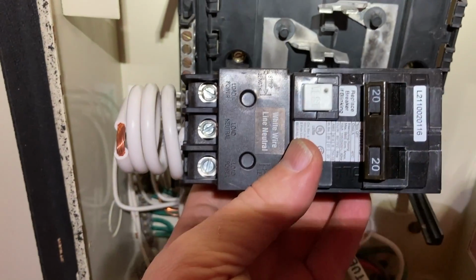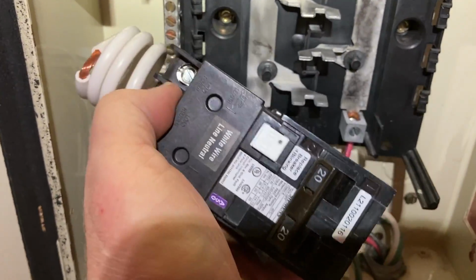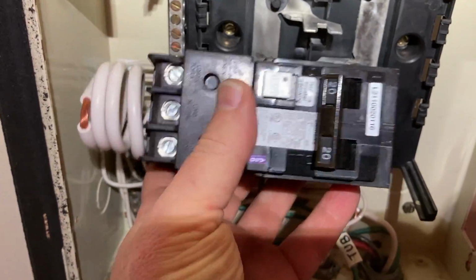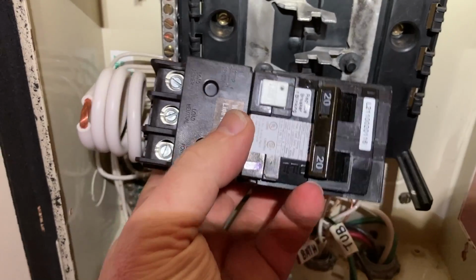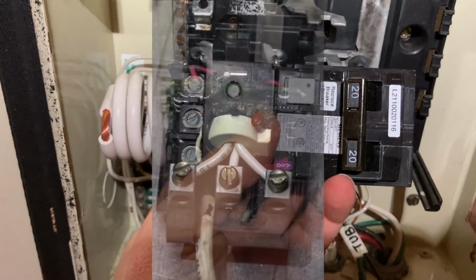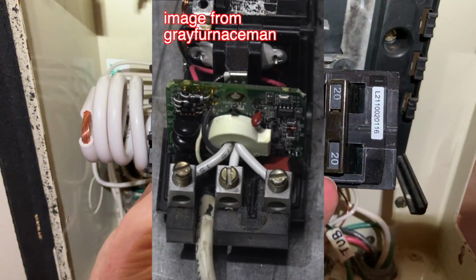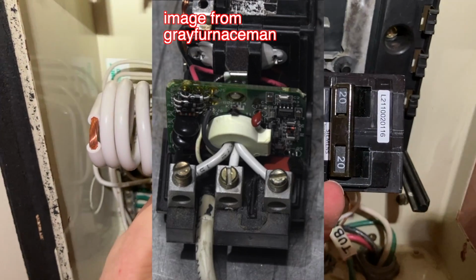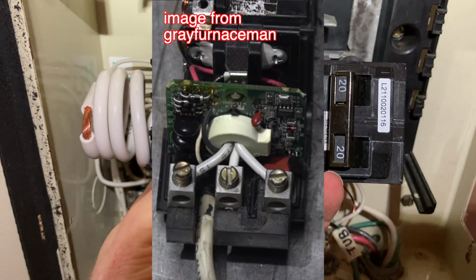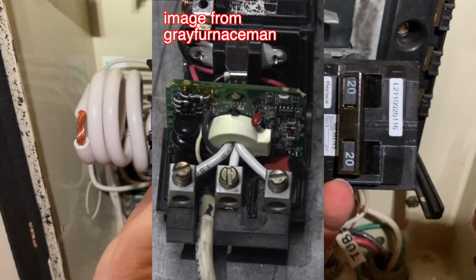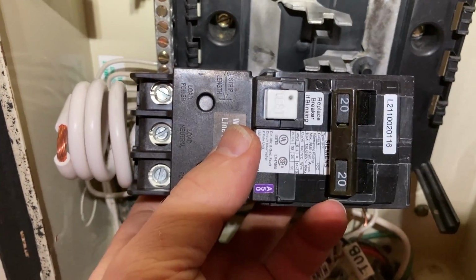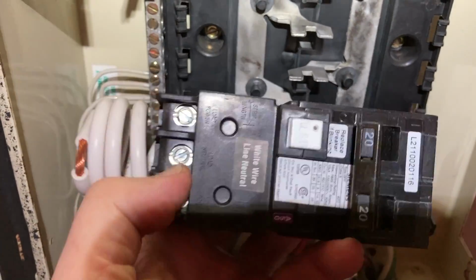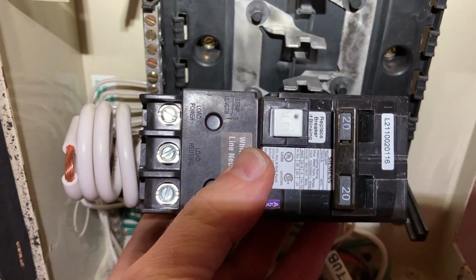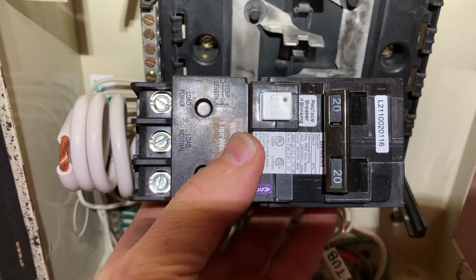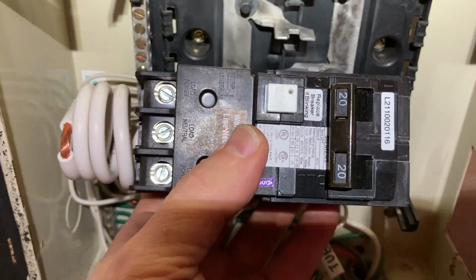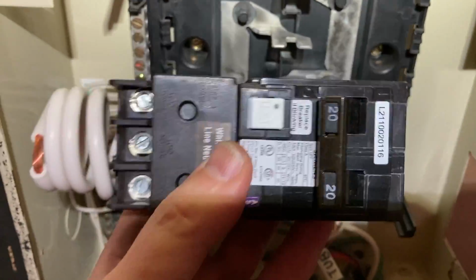You can run these with or without a neutral on the load terminal. All 3 wires go through a current sensing loop inside, which is kind of a big current transformer. It's a powdered iron ring with wire all around it. So as current flows through on the load wires, it causes a magnetic field to be induced in that wire, and that comes to a voltage that some electronics in here can read.